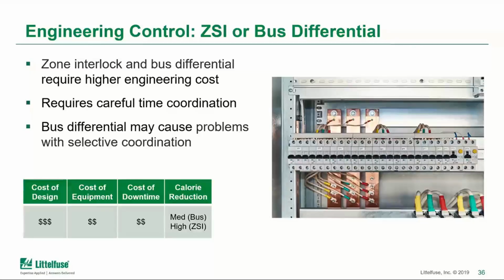In particular, the addition of CTs can be a bit of a bear to deal with, depending on where you have to add those. If those CTs are already in place, of course, then that time is reduced. One more caveat to mention: bus differential is something that could potentially interrupt the selective coordination that you might have built into your system. So if there is a flash, it could take down a little more of the equipment than was originally intended.